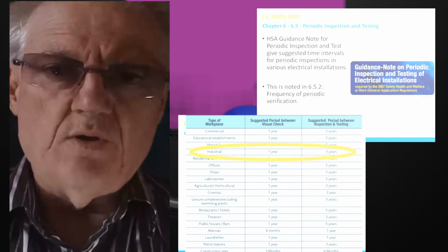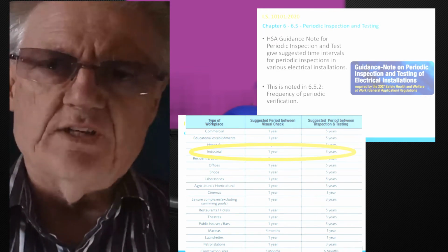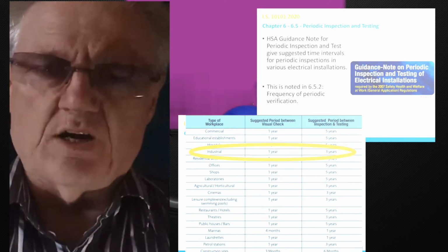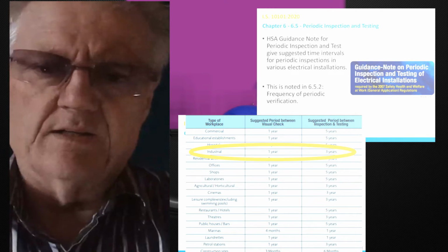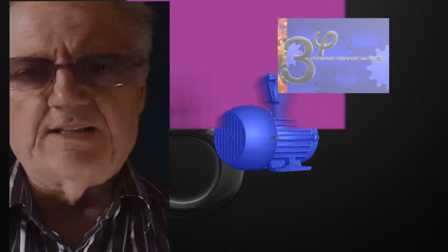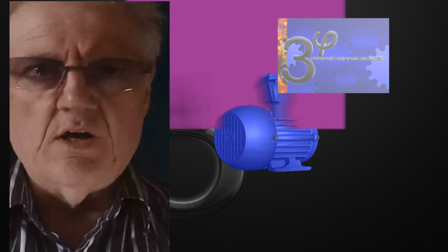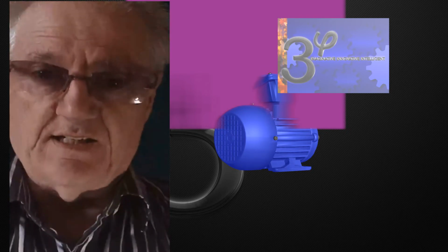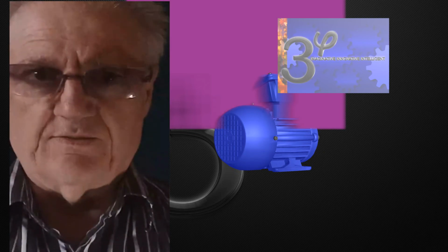In the EU and UK, there are mandatory testing requirements and guidelines for periodic maintenance. On average, 3-phase reliability checks find 10% of circuits with bad resistive defects, and another 10% with warning defects.